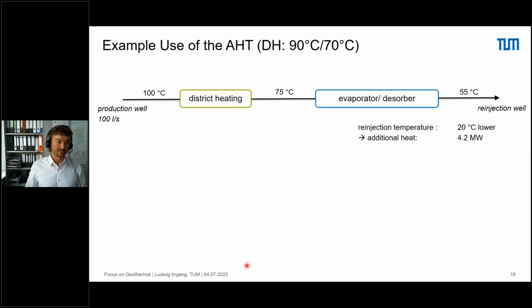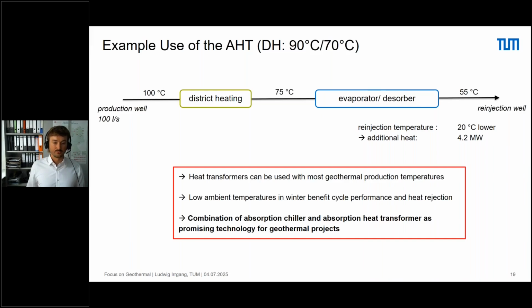And a setup would look like this. We have the production well with 100 degrees production temperature, then the district heating heat exchanger cooling down the brine to 75 degrees, and then additional cooling of 20 degrees with the absorption heat transformer. This could also be interesting for projects where we have very low temperatures in the first place and want to upgrade heat to a useful temperature level. So we identified the heat transformer as a very interesting technology for geothermal energy, also because the low ambient temperatures in winter benefit the cycle and the heat rejection.